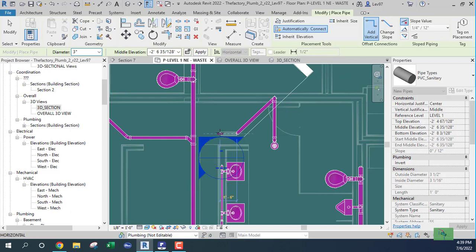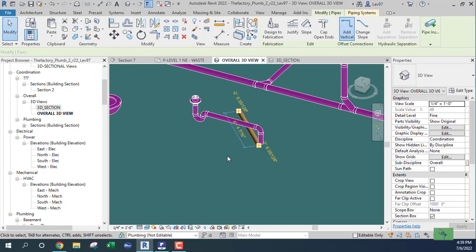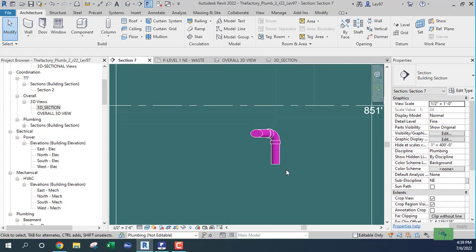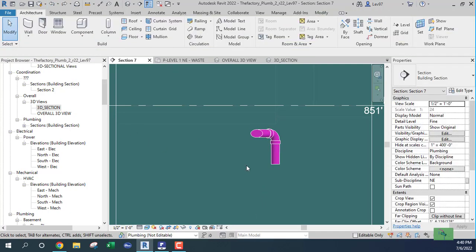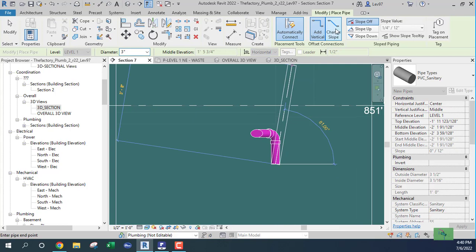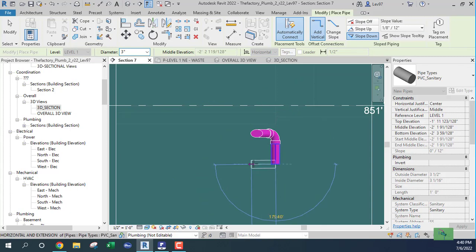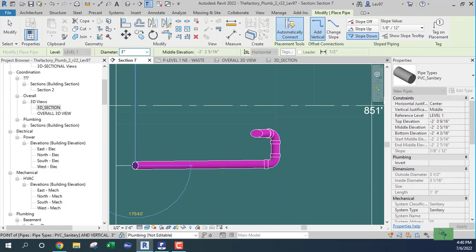I'm going to slope this. Let's go here — erase this, and go back to the first floor section. I'm going to draw my pipe at a slope of one-eighth, because it's more than two inches — otherwise it would be a quarter. So we're sloping down. That looks good.